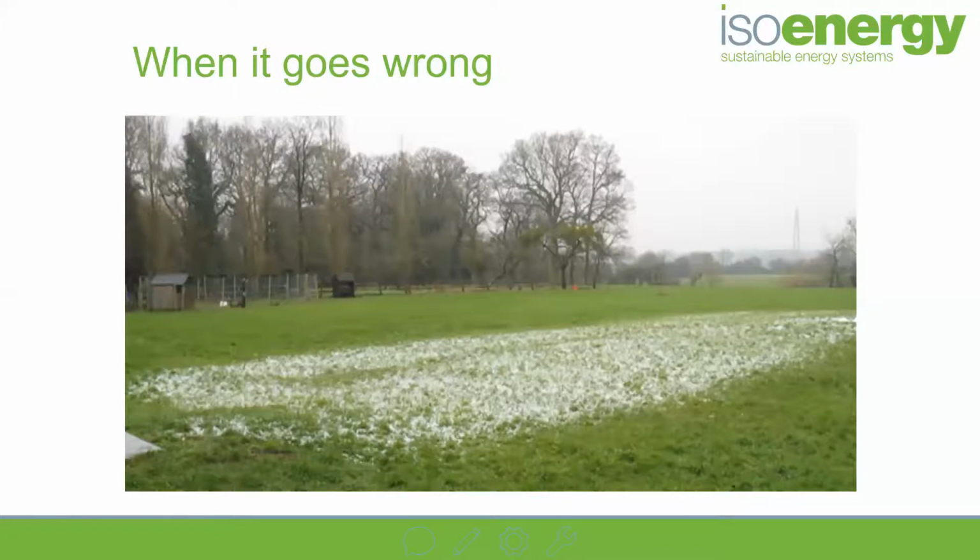So just going back to this. What you're looking to do is take as little energy, I know it sounds ridiculous, but take as little energy as possible over as larger an area as possible, because it is, at the end of the day, the environment that you're relying on for your energy source. You will hear people saying, yes, of course, in your quarter of an acre garden, you could put in 1,000 meters of pipe. Of course, you can physically fit it in, and yes, it is a cheaper solution, but it will fail potentially after a year as the ground gets progressively colder, and the next year it then freezes.